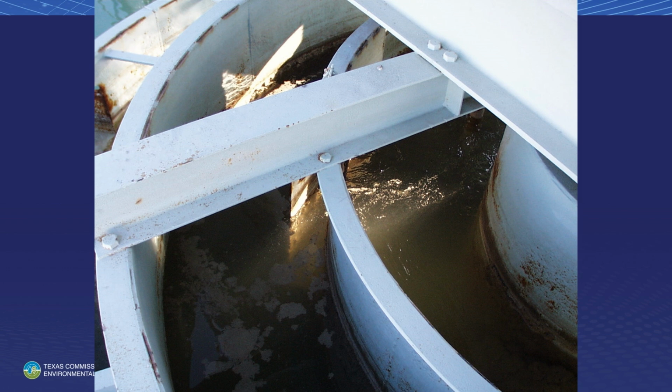If it's set too high, those streaks will be real wide and your flock will be real fluffy and it'll float, and you'll have trouble getting it coming out of the sedimentation basin. It'll be washed out of the box and right over into your filters. So you'll get reduced filter runs and reduced filter life out of your filters. There's all kinds of issues where that's affected your filters.